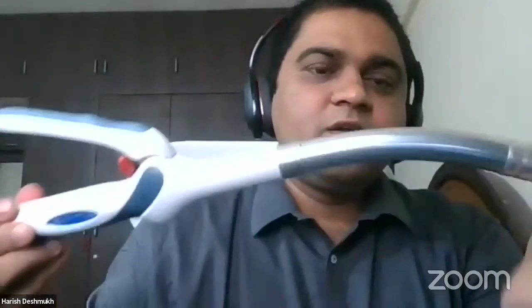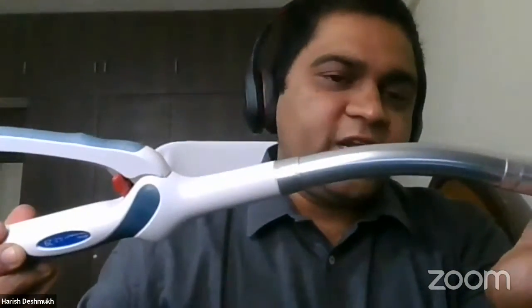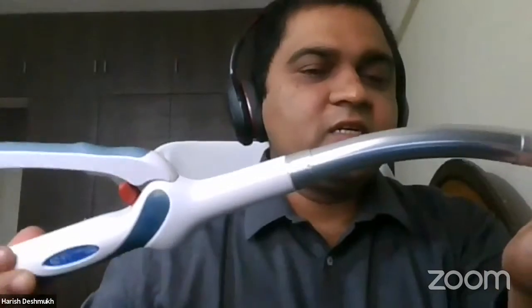Once it is done, the vacuum which is created because of the anastomosis is released, then you can just fishtail it and take it out. You can inspect the donuts in the anvil and the gun to have a safe anastomosis. Thirdly, in these staplers, I showed you basically that this is what the tissue range is, the green color.